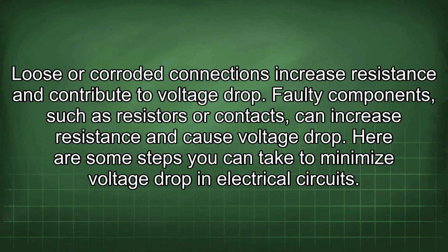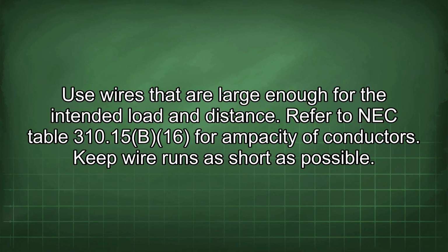Here are some steps you can take to minimize voltage drop in electrical circuits. Use wires that are large enough for the intended load and distance. Refer to NEC Table 310.15(B)(16) for the ampacity of conductors.